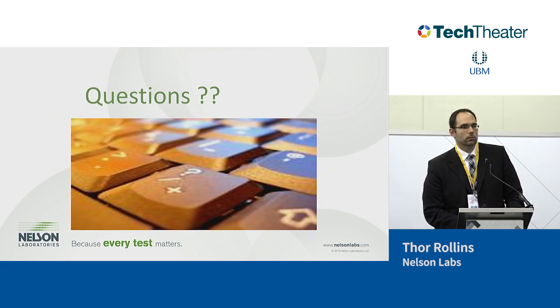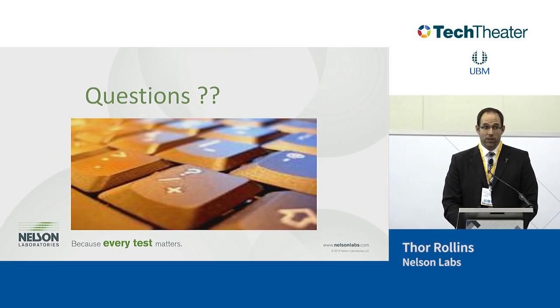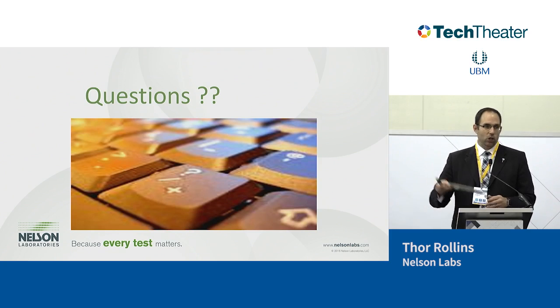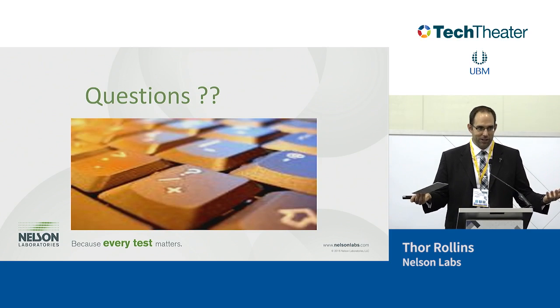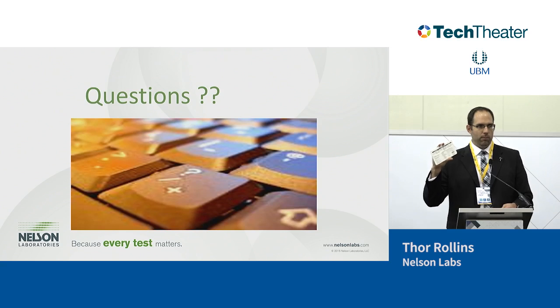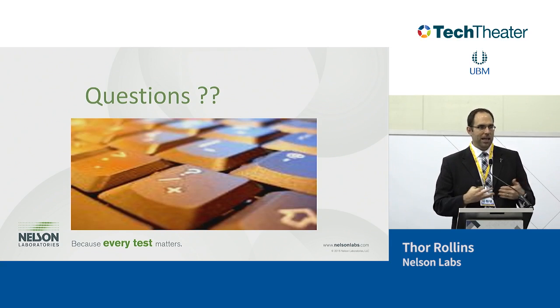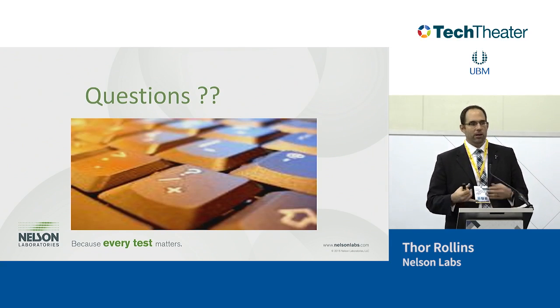What if the use of your device potentially exceeds the requirements for the 10993 code, and you feel that you need to apply more stringent criteria? What would those be? Is it still based on animal experiments, or can you do something more specific to assess more chronic use of the product? Yeah, this is the whole reason we went to a risk-based approach, because this chart really can't envelop everything that's out there today, right? So if you follow this chart, but you're doing a risk assessment, and your risk assessment says, man, this degradation profile of my device is going to make this much more risky, then we have to set up either an animal test or a chemistry test or something to evaluate that risk.